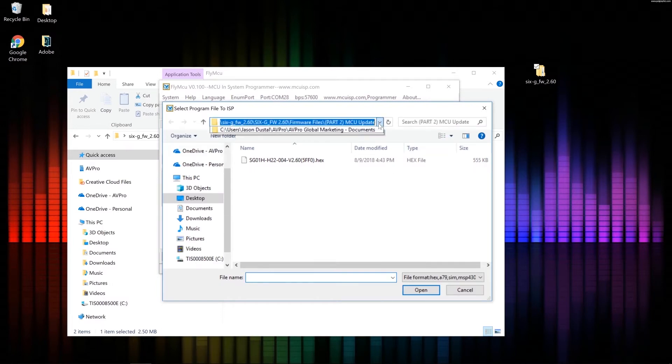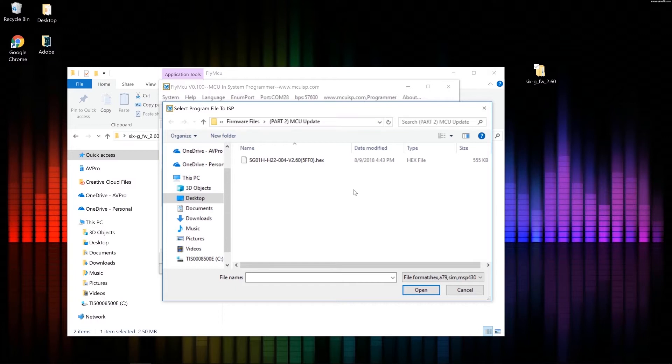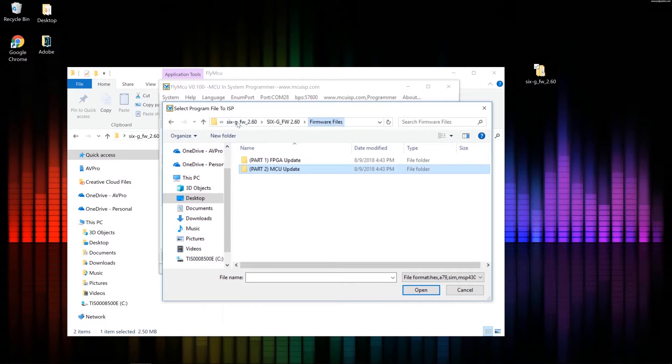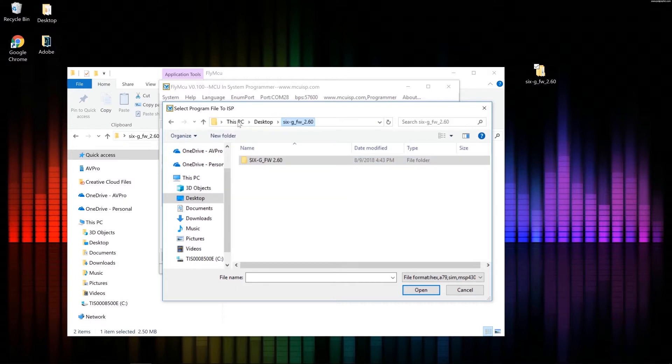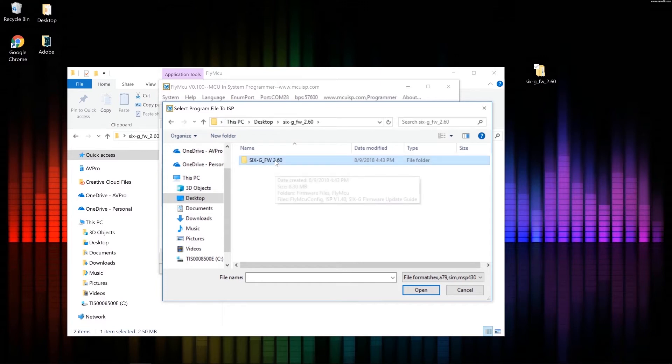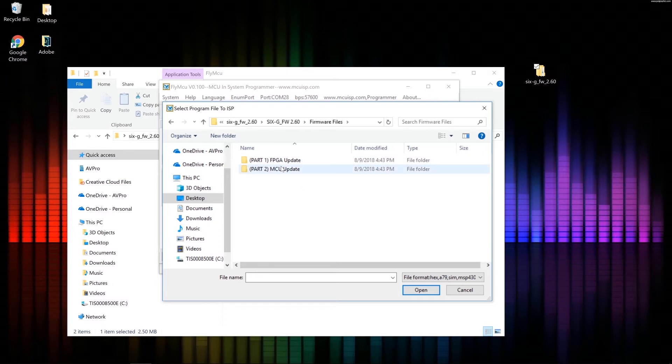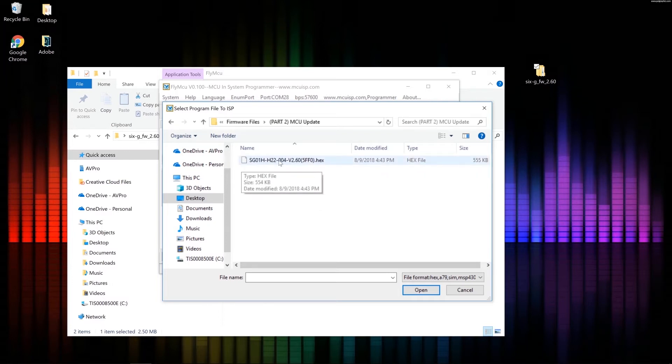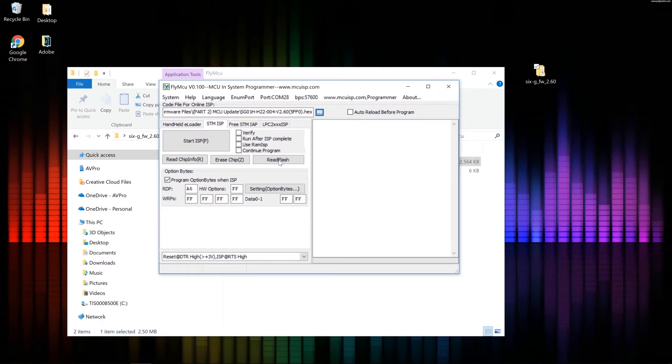So if I go to my desktop, I go to the 6G firmware 2.60 folder. Firmware files. Part 2 MCU update. And there's the hex file right there. Go and double click that. And I'm going to click start ISP.